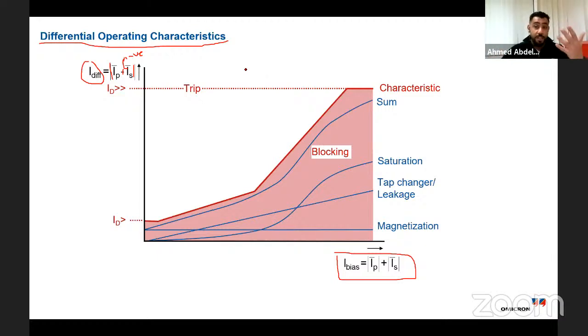The vectorial part happens here, under the calculation of I differential and I bias. So it is a scalar relationship between two parameters, which are the differential current and the bias current. And as we said, you need to go back to the relay manufacturer or the relay manual to get the equation of the I bias.